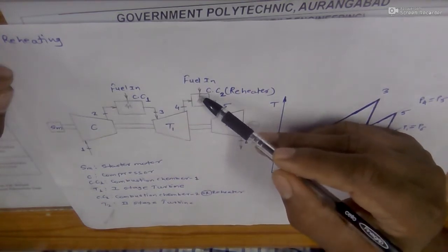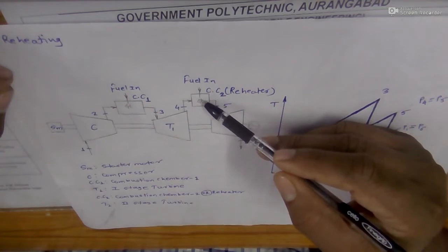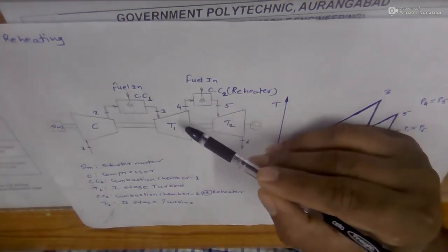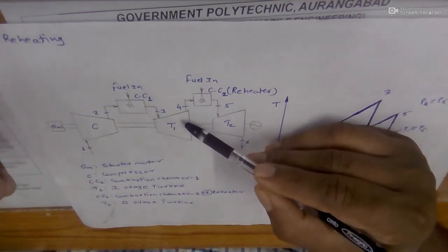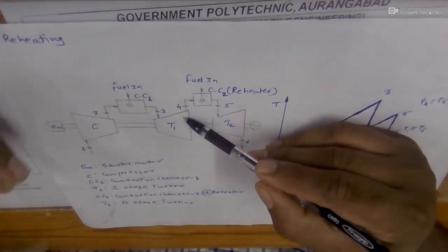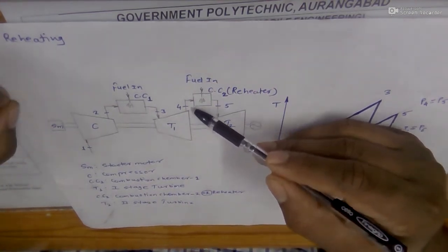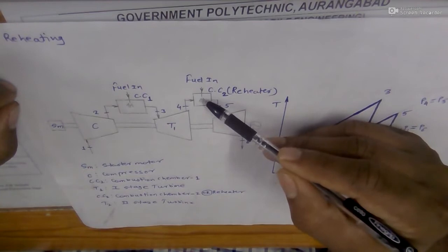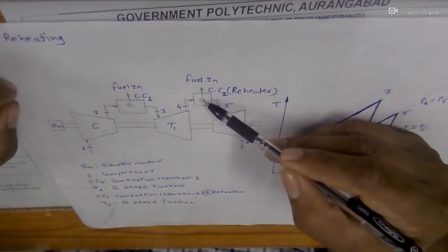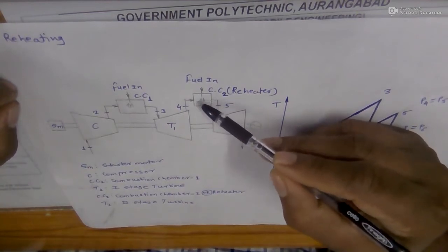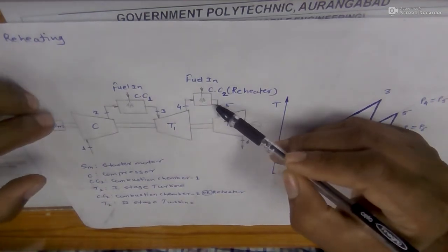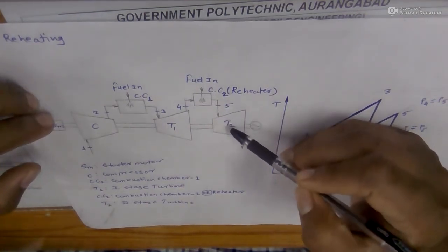After turbine 1 expansion, all those gases are directed to the second combustion chamber. Here also a very little amount of fuel is injected into that stream, and combustion takes place again, because the gases coming out from turbine 1 may contain some amount of heat and can lead to further combustion inside combustion chamber 2. They then expand again, and their expansion is allowed inside turbine 2.